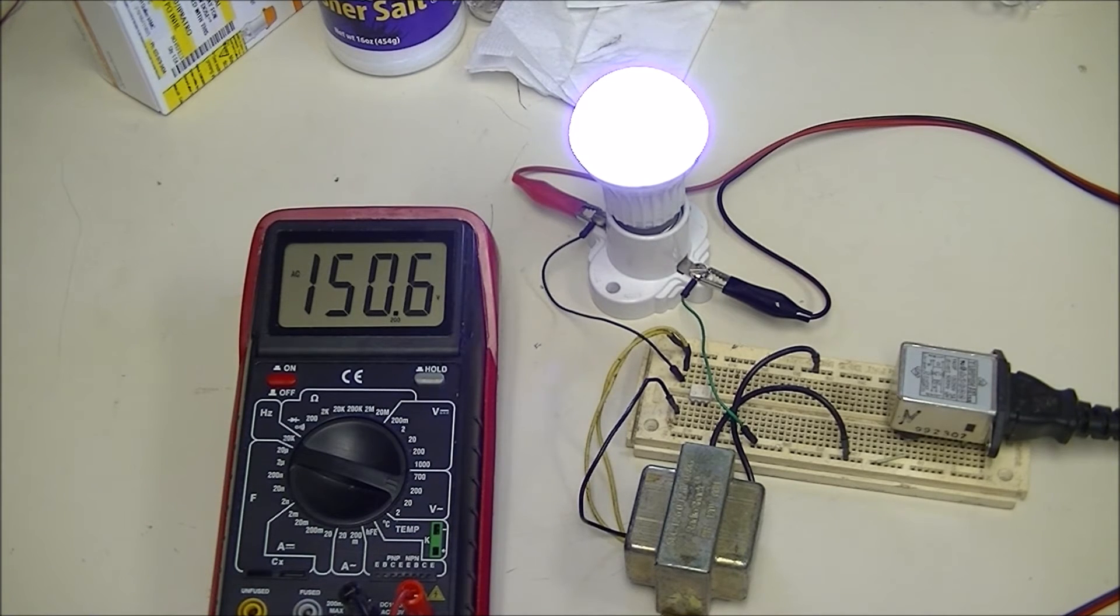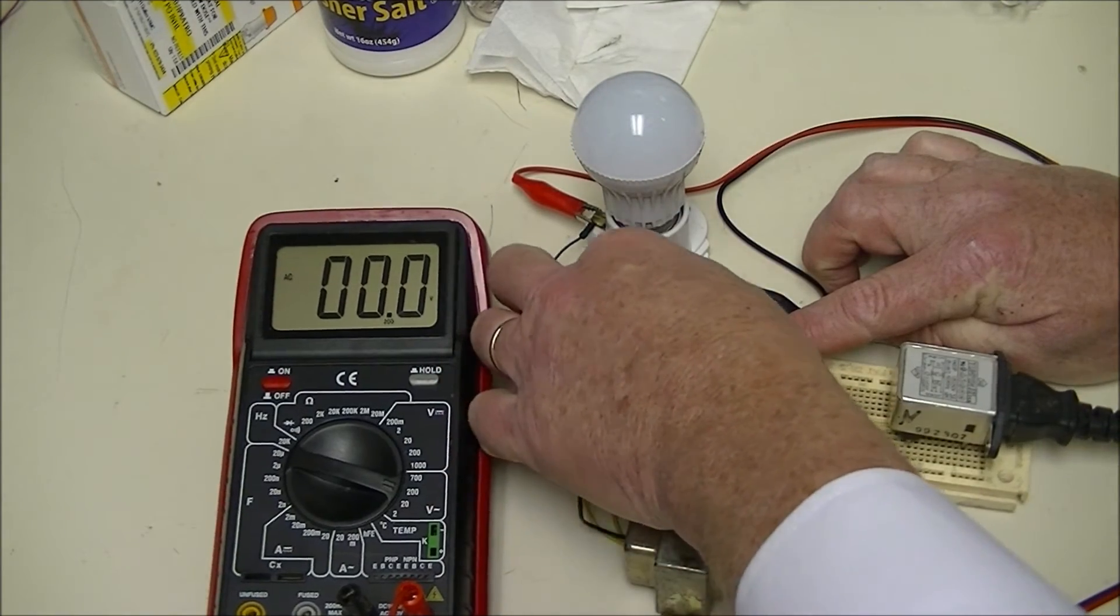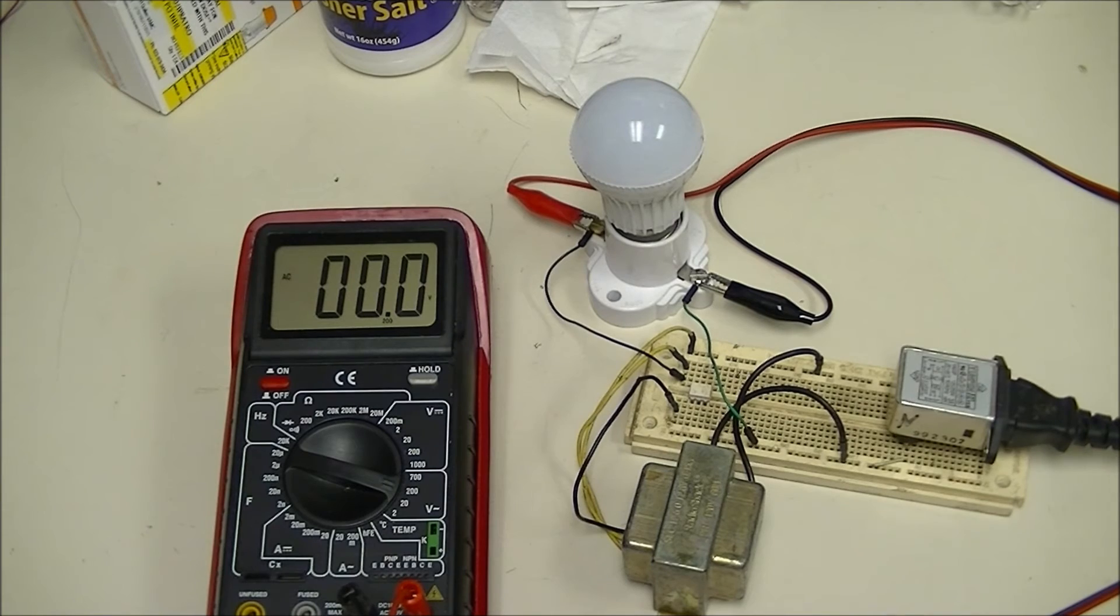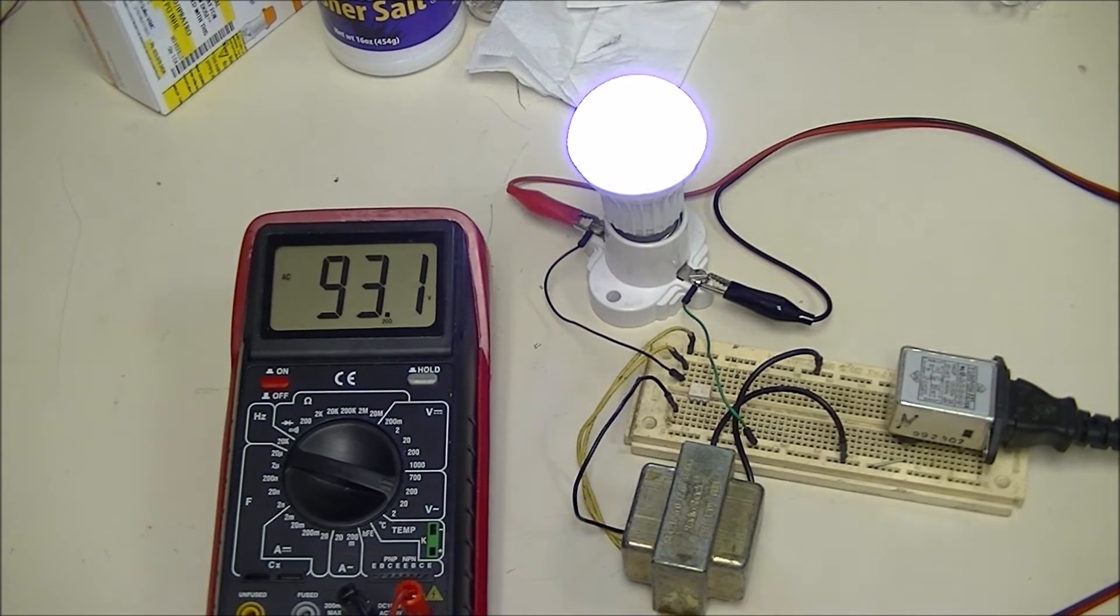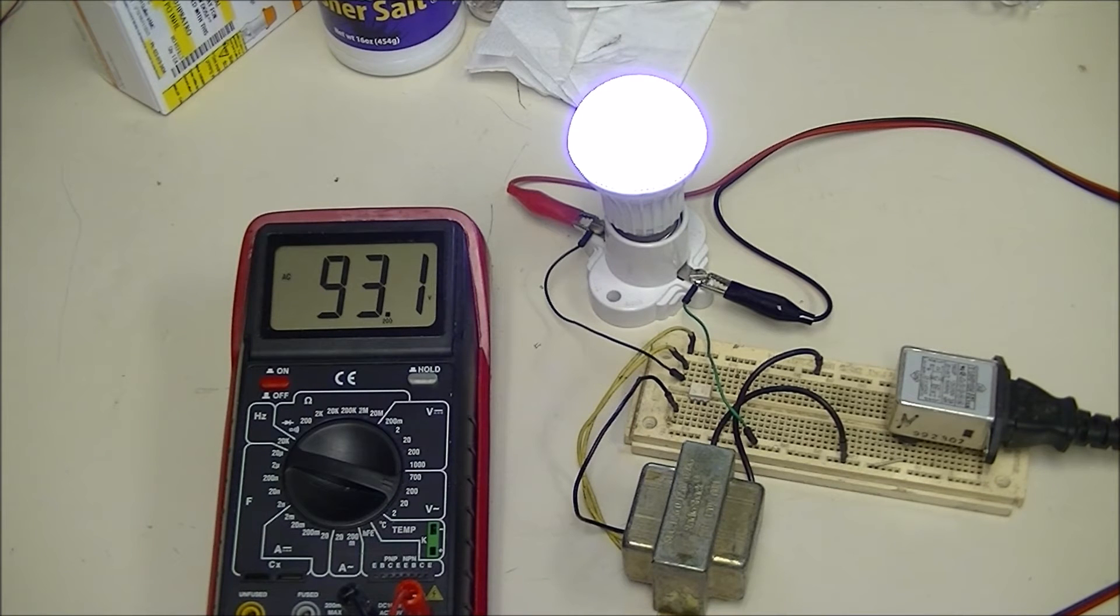Watch the two yellow wires. I'm going to reverse them. Now I've dropped it to about 90 volts. If you need an oddball transformer like 150 volts, you can use this to make one.